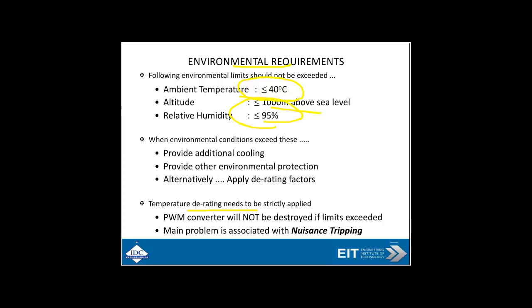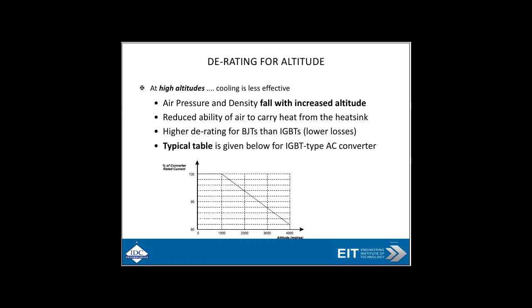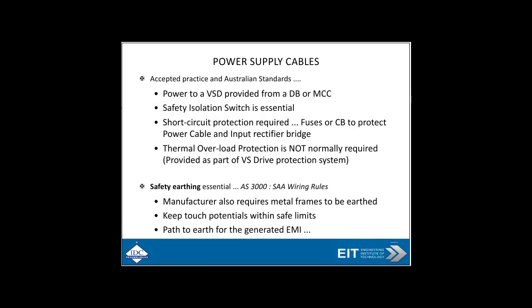You need to do temperature derating — for example, if you go into temperatures above 40 degrees, provide additional cooling. There is a typical derating curve: as your temperature goes up to 55 degrees, you drop the converter current by 50 percent, so that's obviously very important. The same issue applies at high altitude, where cooling is less effective, so you need to reduce the rated current. You can go all the way down to 82 percent at 4,000 meters, which is pretty high.